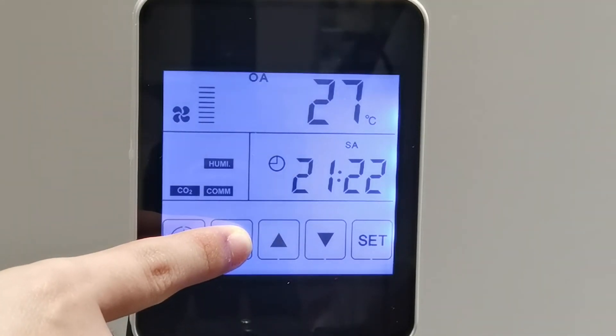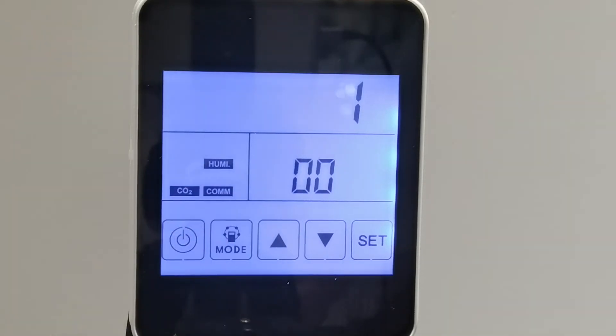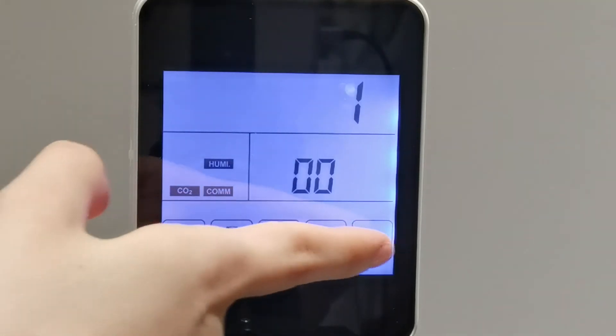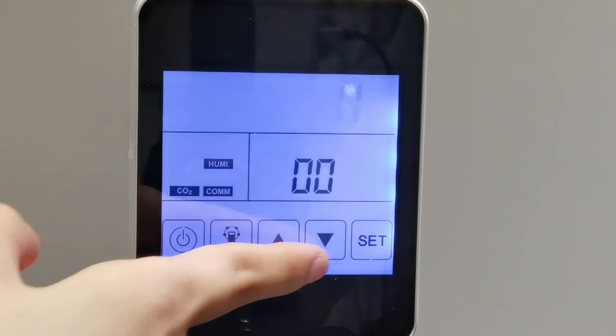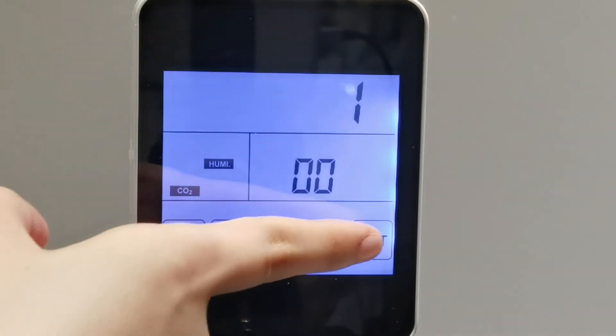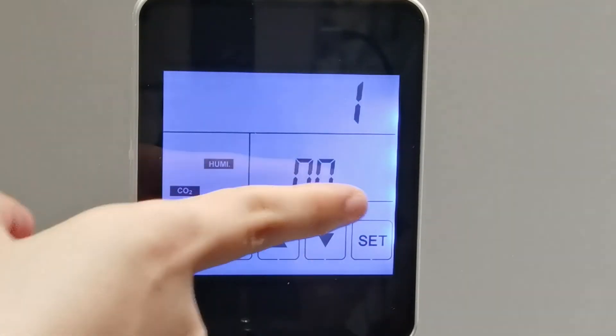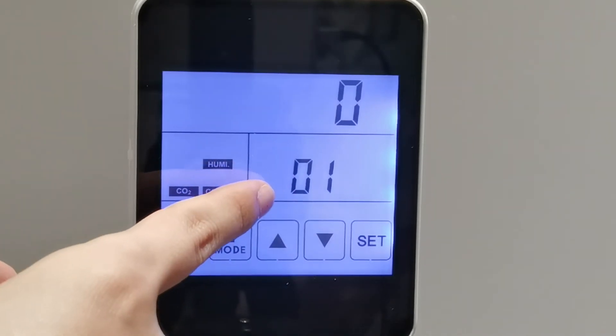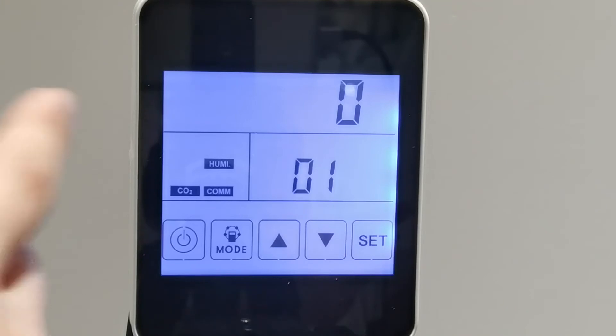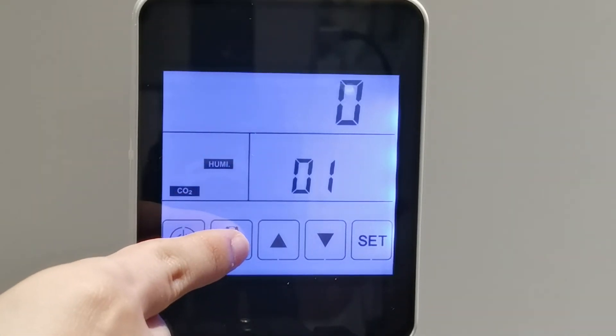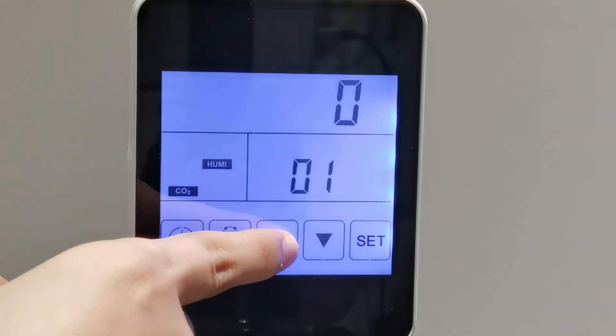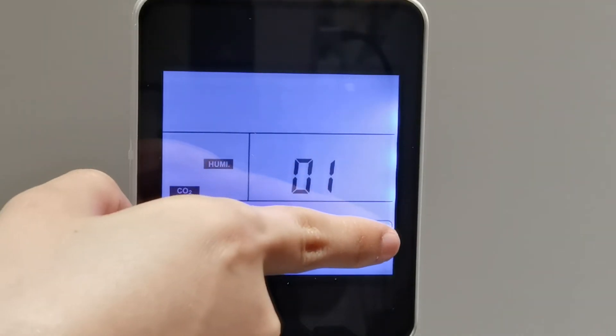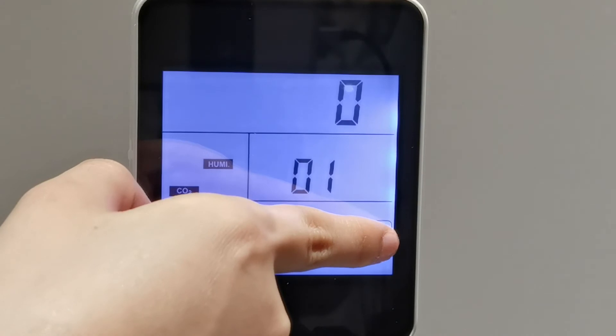Let's press the mode button for 6 seconds to enter parameter 00, which refers to power-on auto restart. 0 is invalid, 1 is valid, and the default value is 1. Press the set button to save and one more time to enter parameter 01. Parameter 01 refers to the supply air electrical heater being available or not: value 0 is unavailable, value 1 is available. The default is 0. After your ERV is connected to the electrical heater, you can choose value 1 to activate this function.